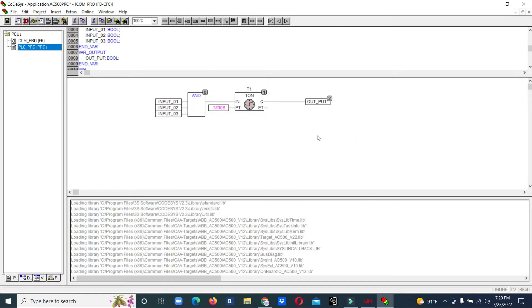So now we have made the function block: if you get any three inputs together, after the time delay it will enable the output. We have eight digital inputs, and for each combination of three digital inputs we do not need to make individual AND gates, timers, and outputs. We made one function block, and using it we can make the program easily.